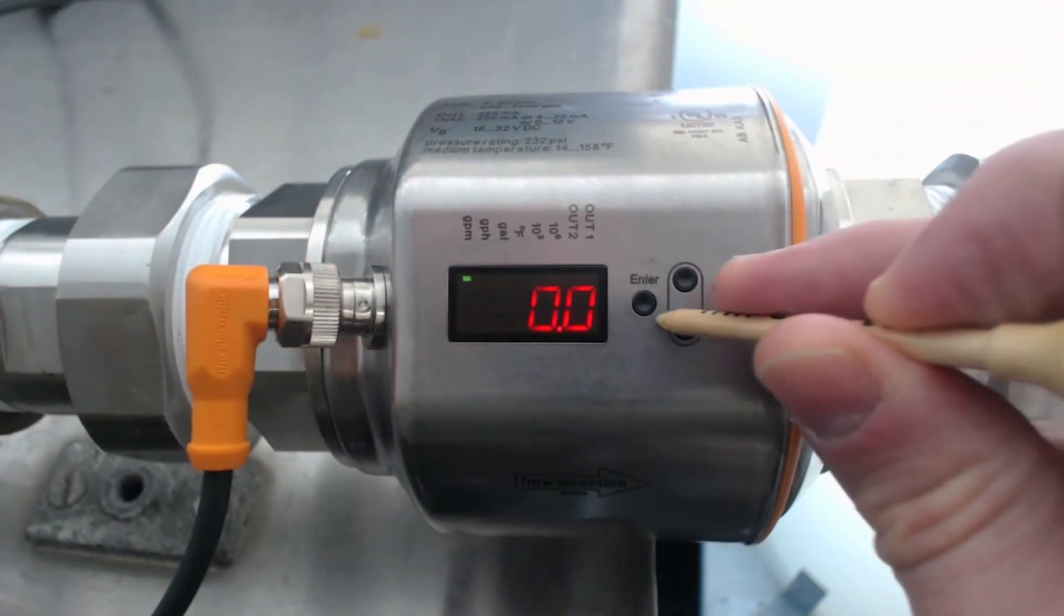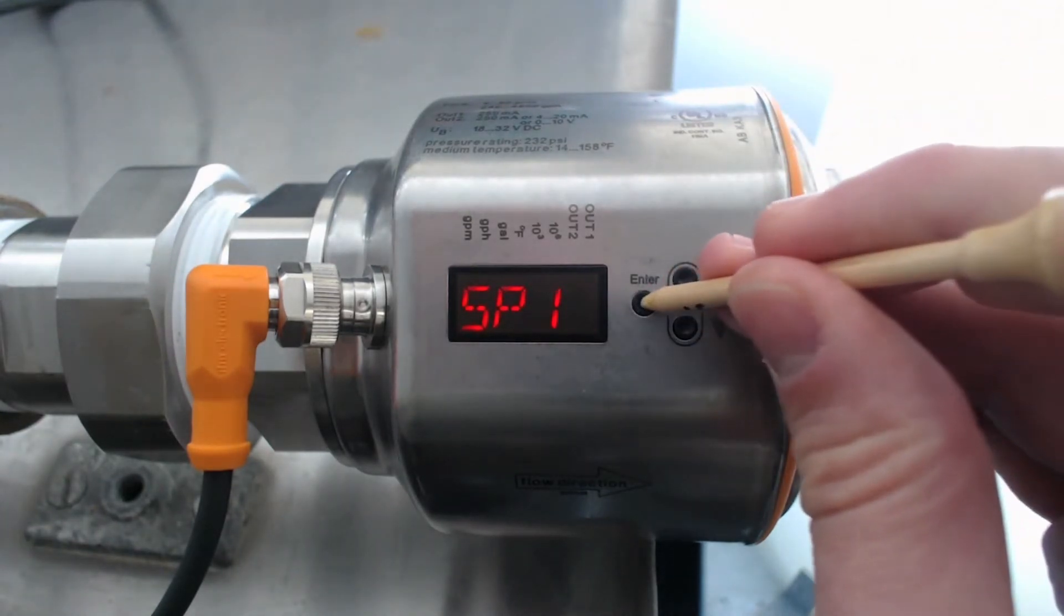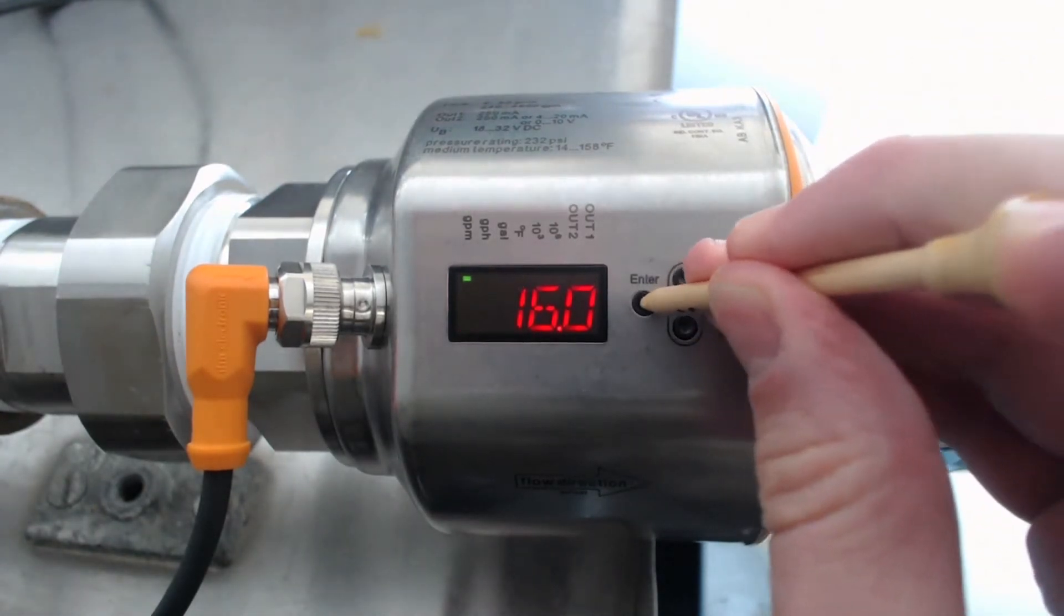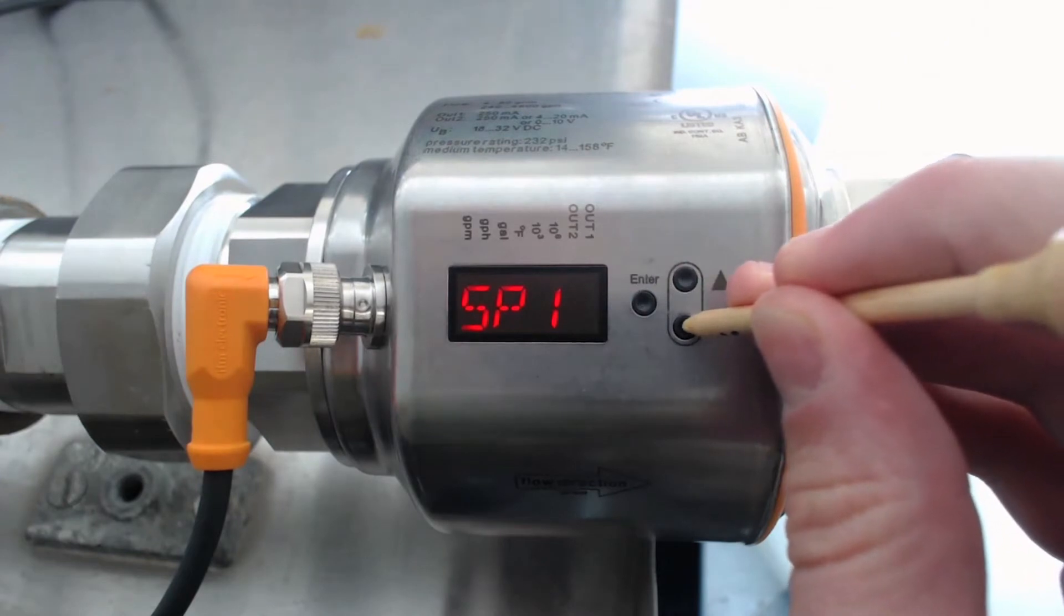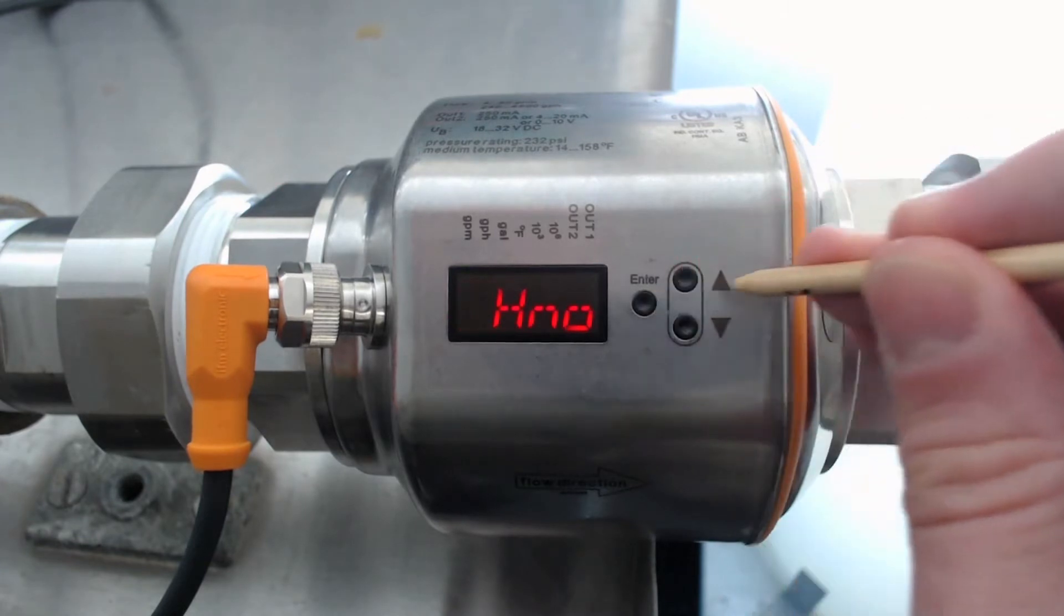Looking at an IFM magmeter, press Enter for the menu. At SP1, press Enter again to set the switch point. For output 1, push the lower button until OU1 appears. Press Enter.